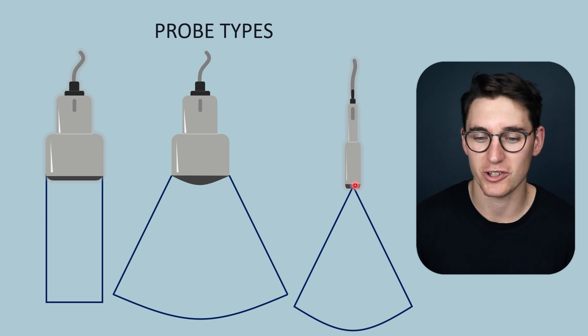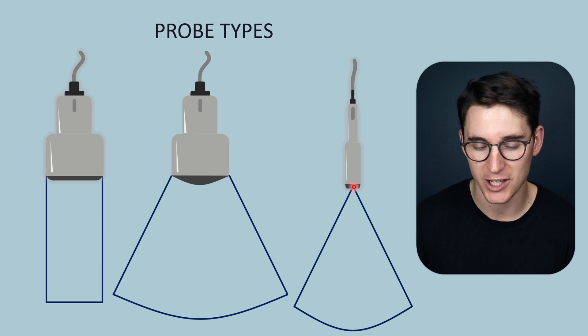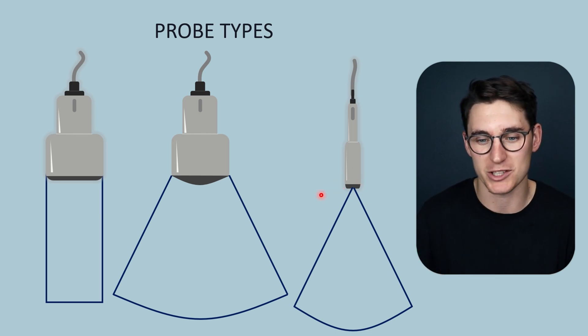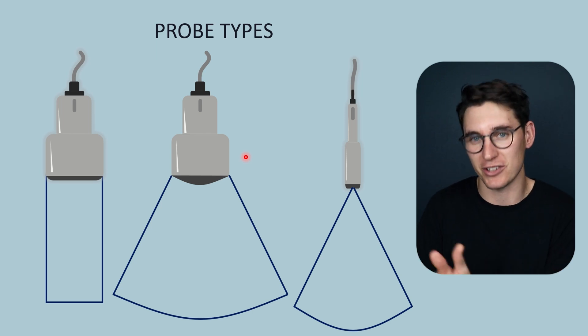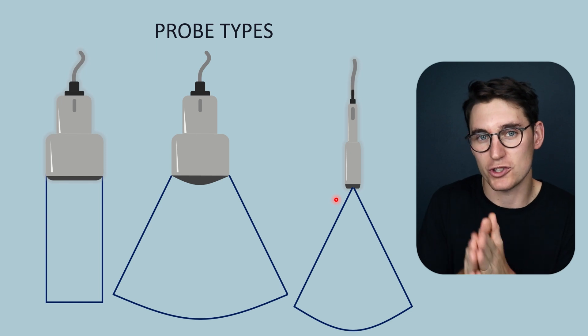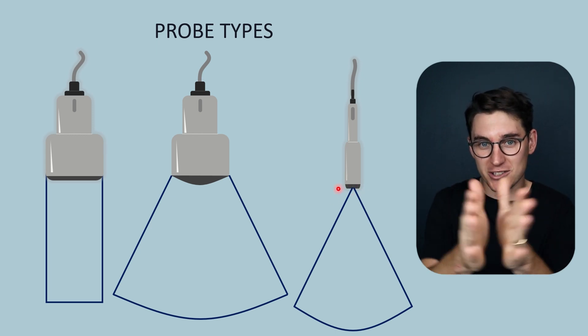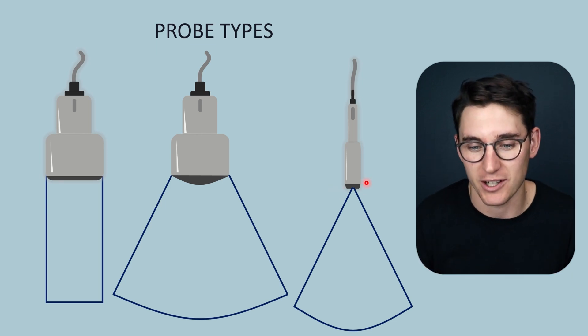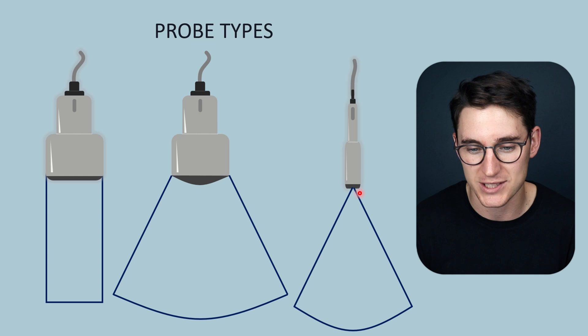The phased array probe has a much smaller face to the transducer and it has a pure sector — not a blunted sector. We get this fanning out of the ultrasound wave. The phased array probe has much fewer transducer elements than our linear and curvilinear probes. Linear and curvilinear probes generally have 200 to 300 discrete transducer crystals, while the phased array probe generally has 64 to 128. This smaller surface area still allows a large field of view — for example, we can get between the ribs and still capture the entire heart within our field of view.